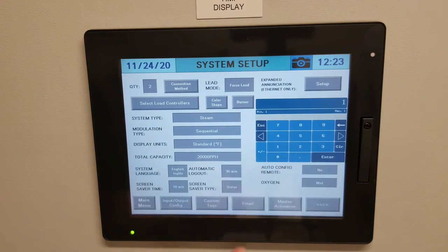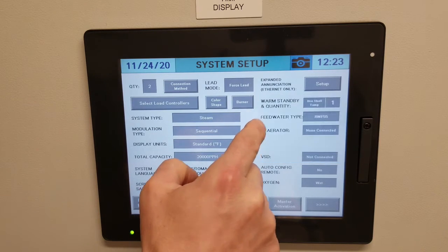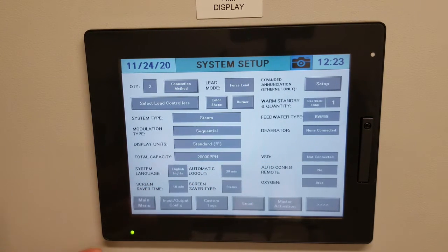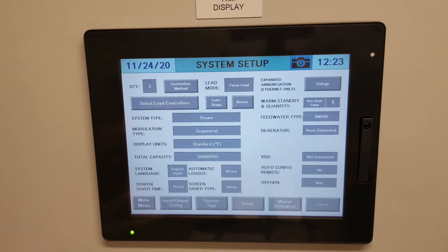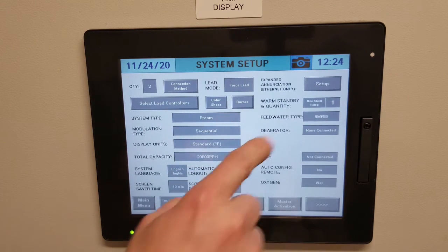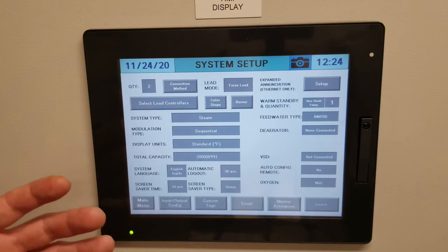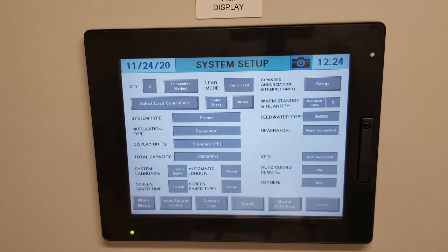Next, you'll see a number for the warm standby. In our case we can only select one because we only have one lag boiler. But if you have three, four, or five lag boilers, this tells the system how many lag boilers to keep in hot standby. Where this is very handy: if it's summer load and only one boiler runs at a time, there's no need for three other boilers in hot standby. Set it to one and it keeps the first lag boiler on hot standby; the others remain off. If the lead boiler shuts down and the lag takes over, the system automatically initiates the next lag boiler in sequence for hot standby. Feed water type is RW/SS; no DA connected, no VFD. We may have VFDs on local boilers, but unless using Modbus for additional information, always leave this as not connected.